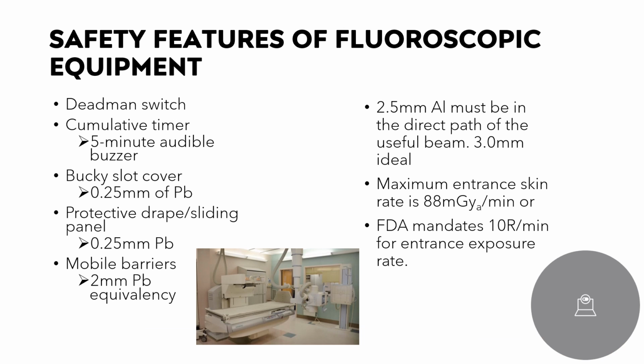So, some safety features of fluoroscopic equipment. There needs to be a dead man switch, which means that if your foot is taken off, the fluoro is automatically discontinued. It needs to have a cumulative audible 5-minute timer so that everybody knows how long live radiation has been going off with people in the room. As I said, the Bucky slot cover should be 0.25 millimeters of lead. The protective drape or sliding panel needs to be 0.25 millimeters of lead. Any mobile barrier needs to be 2 millimeters of lead equivalency. 2.5 millimeters of aluminum must be in the direct path of the useful beam, and 3 millimeters is ideal.